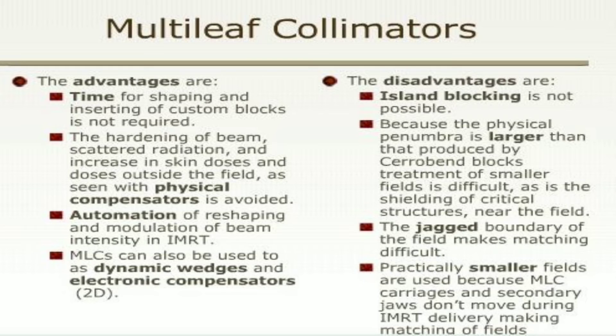Disadvantages of multi-leaf collimators include: island blocking is not possible because the physical penumbra is larger than that produced by Cerrobend blocks. Treatment of smaller fields is difficult, as is the shielding of critical structures near the field. The jagged boundary of the field makes matching difficult. Practically, smaller fields are used because multi-leaf collimator carriages and secondary jaws don't move during IMRT delivery, making field matching difficult.